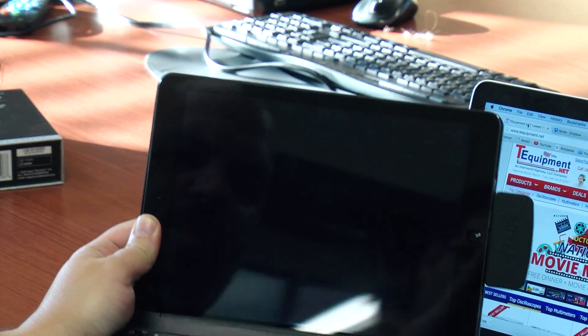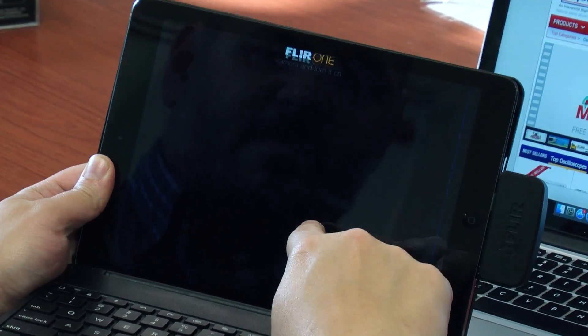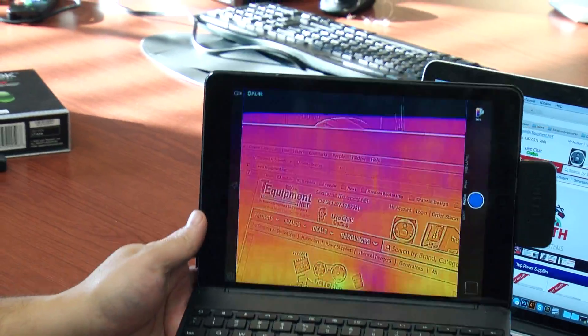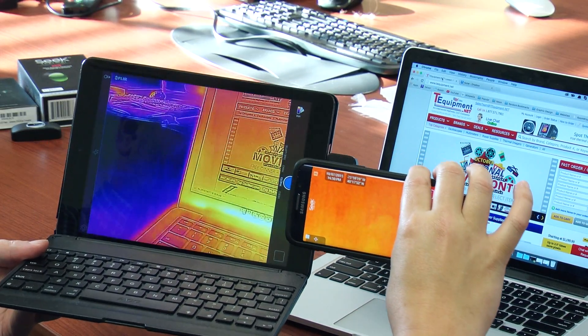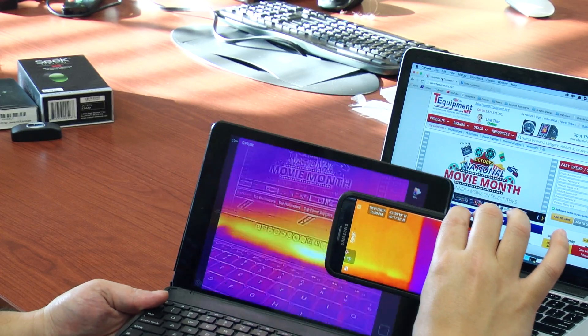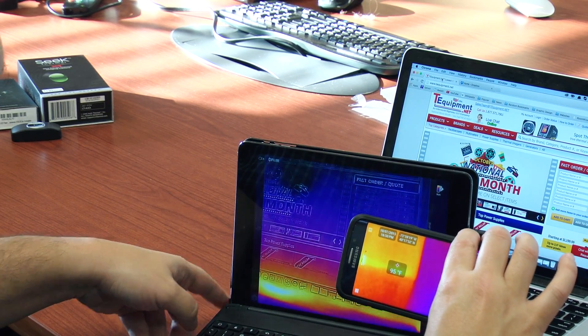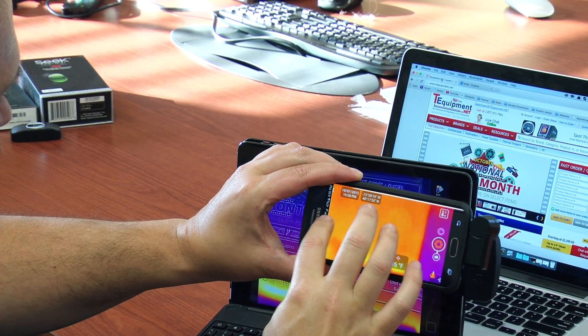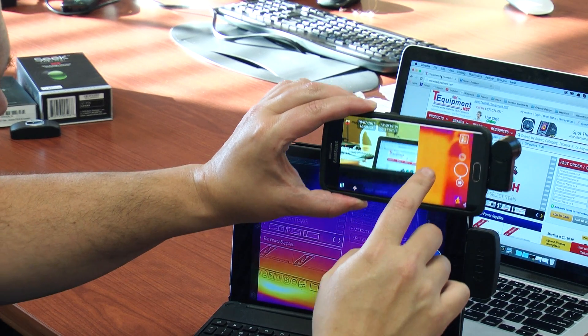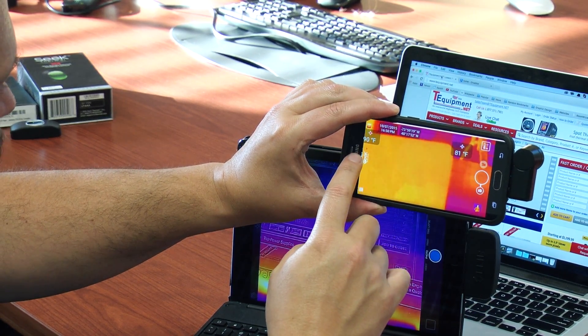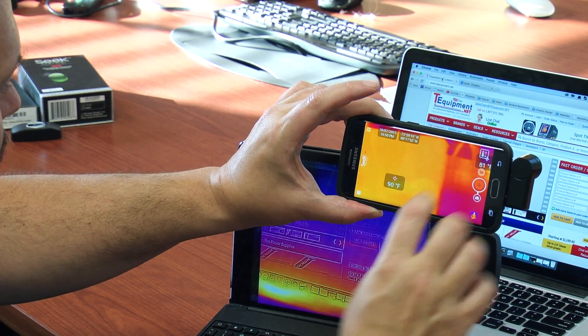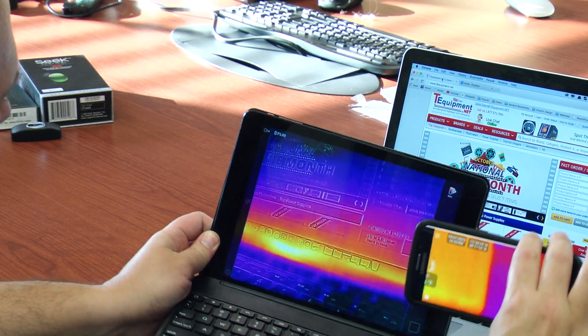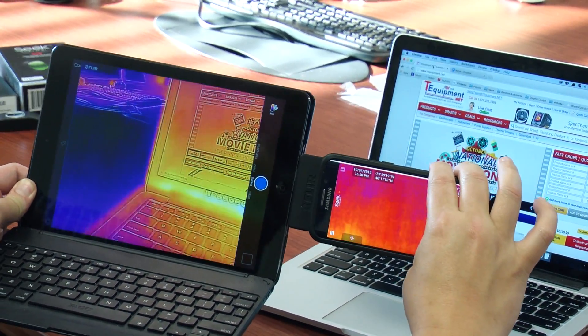Now we want to compare this against what you see with the FLIR One. This happens to be the FLIR One for an iOS device. You'll notice right away that with the FLIR One versus the same image, you can't really tell exactly what it is you're looking at, because FLIR has what's called their MSX enhancement, which will take the visual image and overlay it with the thermal. What you can do here is go into split screen mode, and it'll actually give you a split of the visual and the thermal all in one shot. It still even shows you the hotspot data, so you can still see what you're looking at, but you don't get the visual enhancement that you get from the MSX when looking at the camera directly.